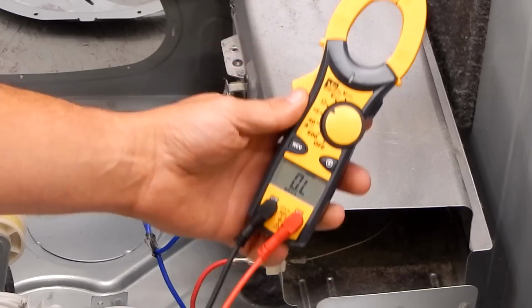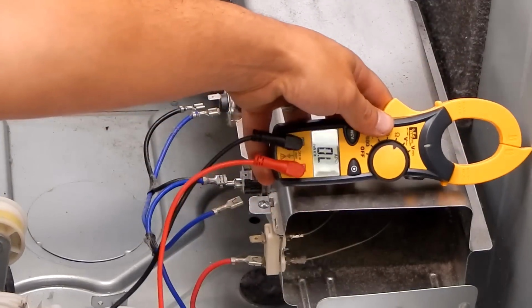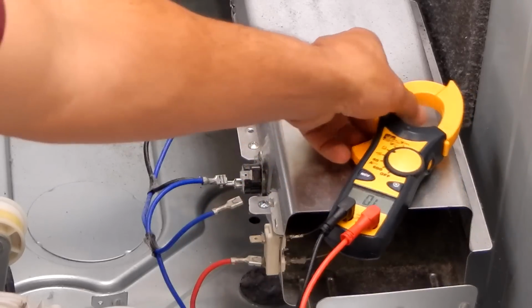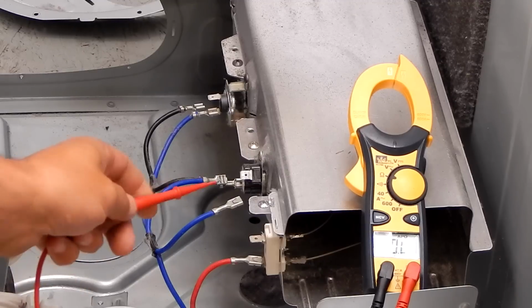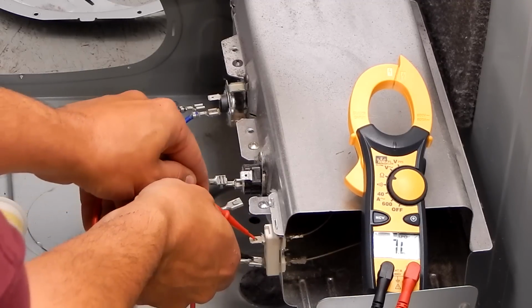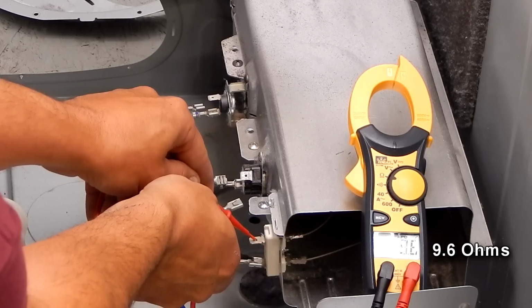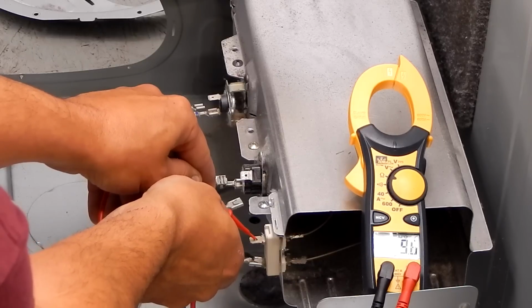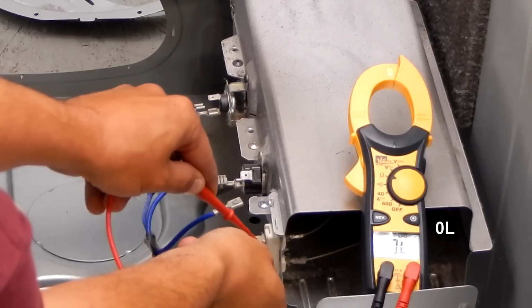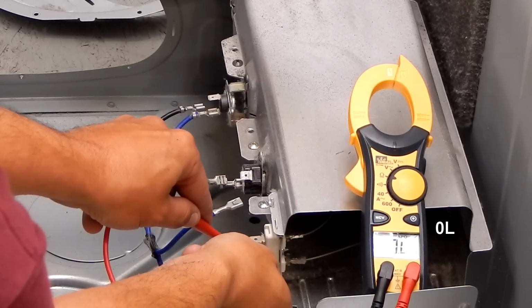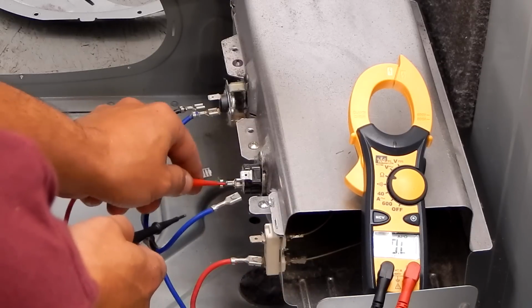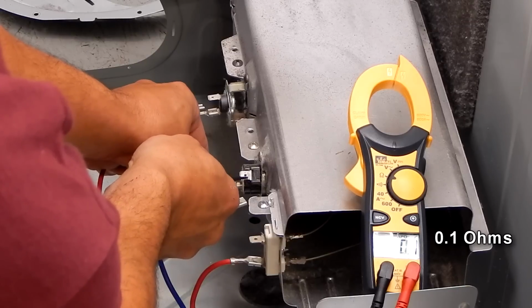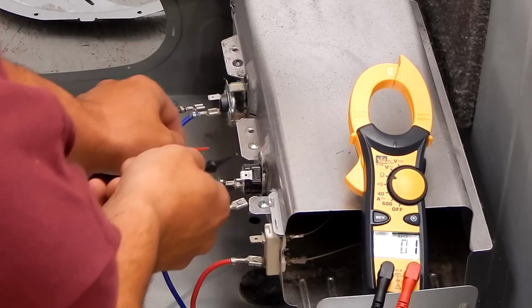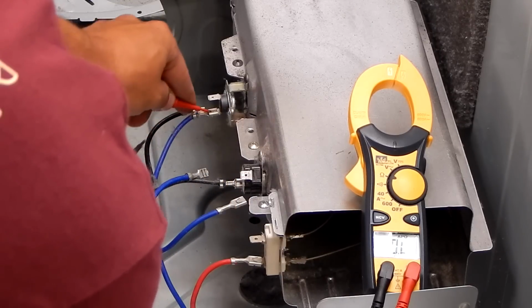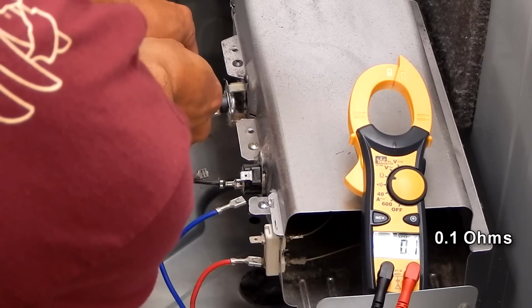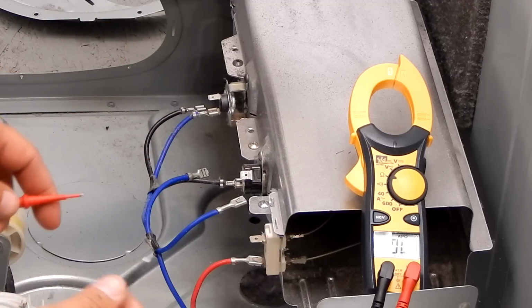Basically you want to set your meter to ohms. And go ahead and check the heating element first. And we're getting 9.6, 9.7. The heating element is good. We'll check it to make sure it's not shorted to the frame. Nothing. And nothing. So the heating element's good. Let's move on to the next thermostat, your high limit. And 0.1. That's good. And we'll go to the thermal cutoff. And 0.1. And that's good.